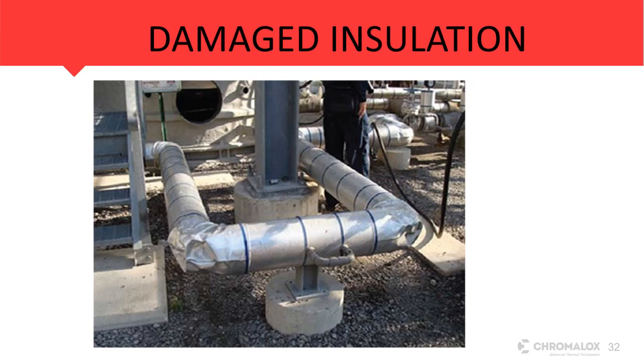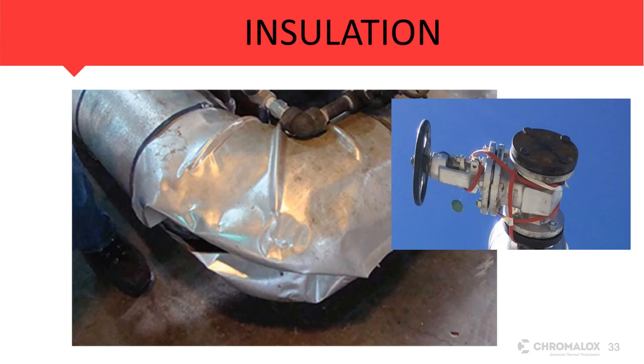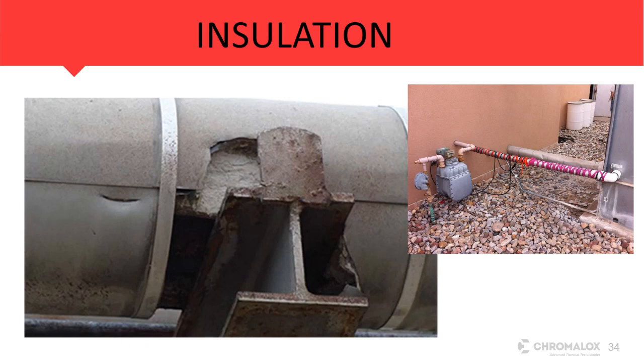Another thing I'll mention is it appears he probably has a steam hose and he's shooting steam up underneath the insulation to try to thaw it out if it's cold. That can cause a lot of issues. Any place we have insulation that's damaged, as you see in this picture, water is going to ingress into there. You're going to get a cold spot that's not going to be able to maintain the temperature, or we're going to have heat loss coming out of there.